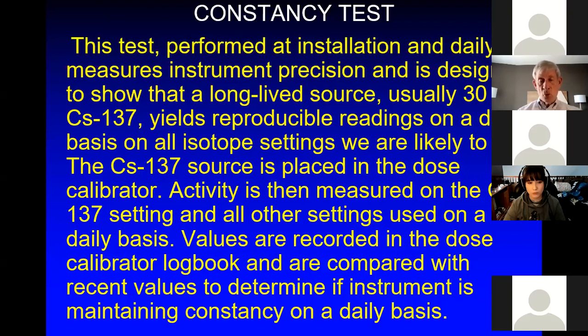We take that cesium source. We put the cesium source in the dose calibrator and we read the cesium on the cesium setting. That is a mini accuracy test. We're checking cesium on the cesium setting. Better give the right answer.